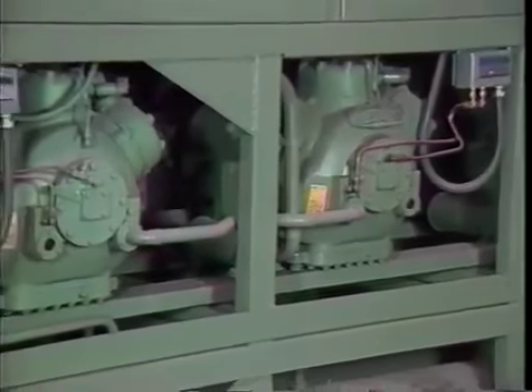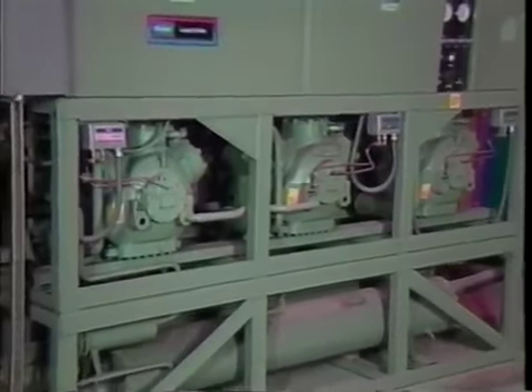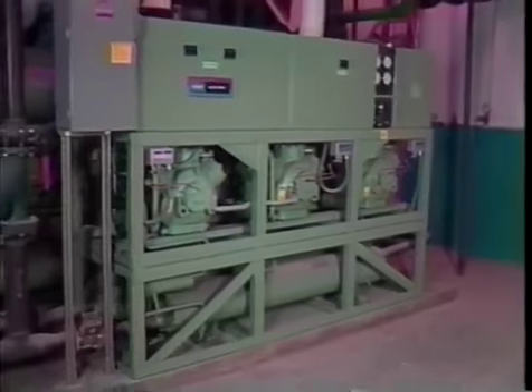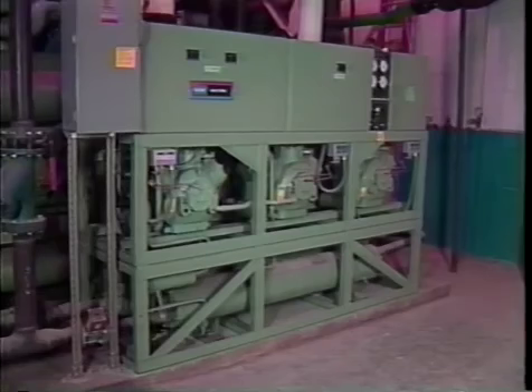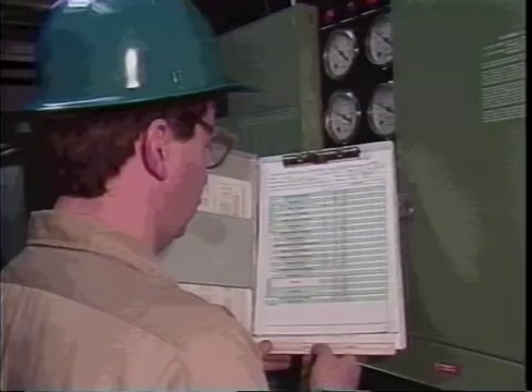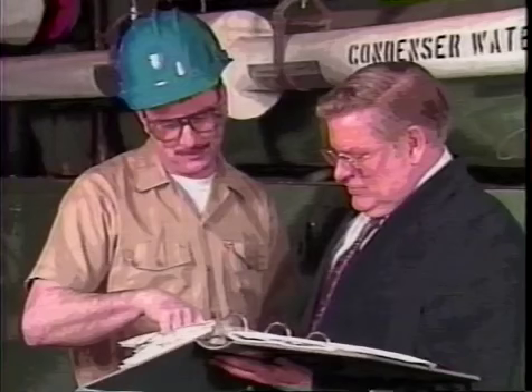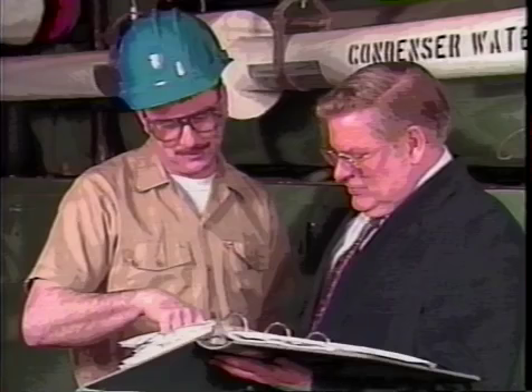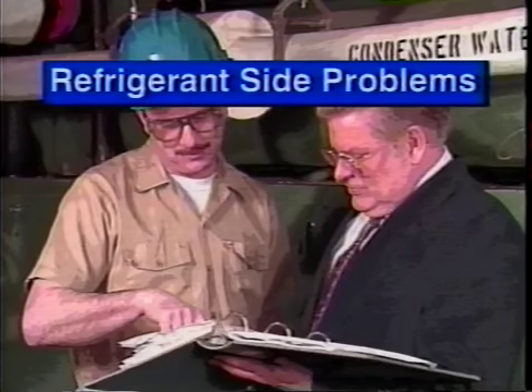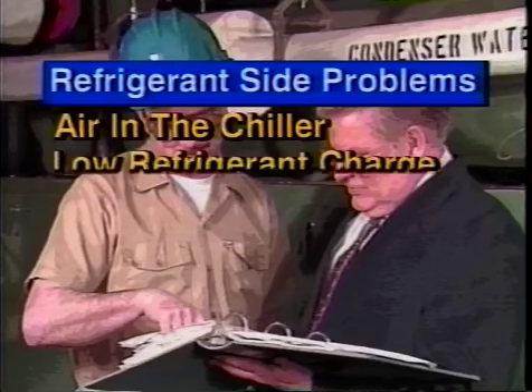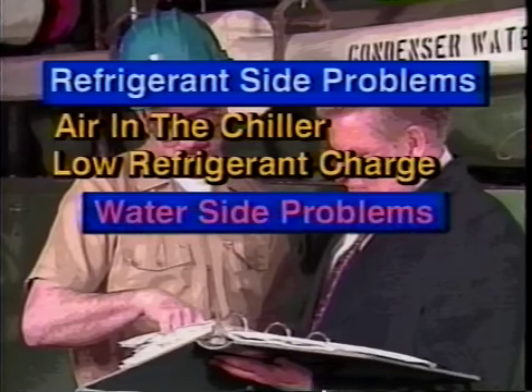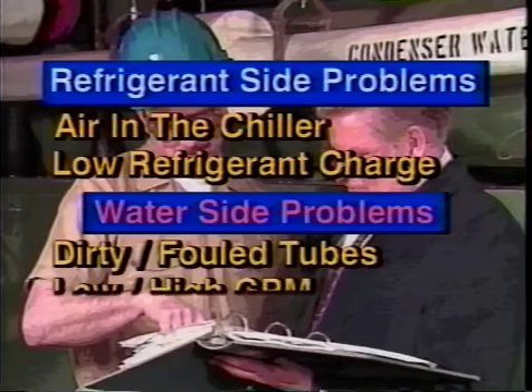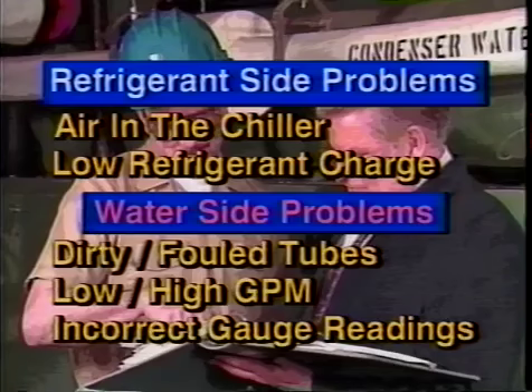For chillers with 2 refrigerant circuits, a set of data should be taken for each circuit. For the purpose of keeping this program comprehensible and focused, we will treat the chiller as a single circuit machine and will only use one set of data for our troubleshooting analysis. After taking the readings, compare the current operating temperatures and pressures with the design conditions and previous operating conditions to spot any trends which might be leading to trouble. Using the log sheets will help identify refrigerant side problems, including air in the chiller, low refrigerant charge, or water side problems, including dirty or fouled tubes, low or high GPM, and incorrect gauge readings.